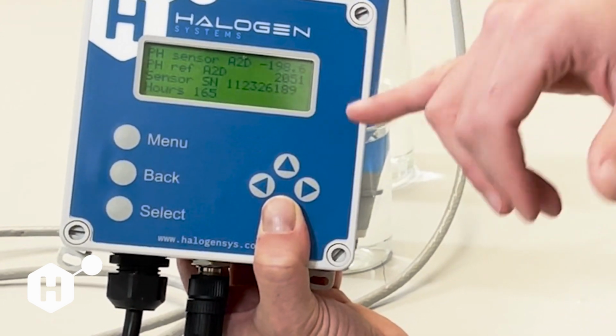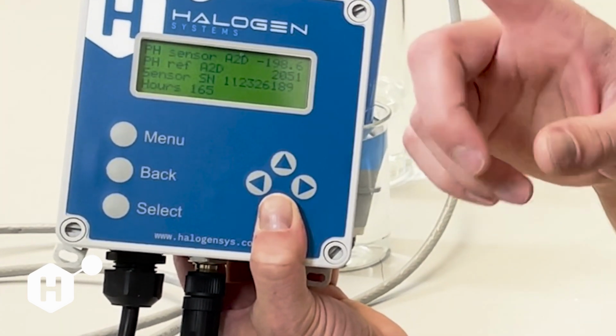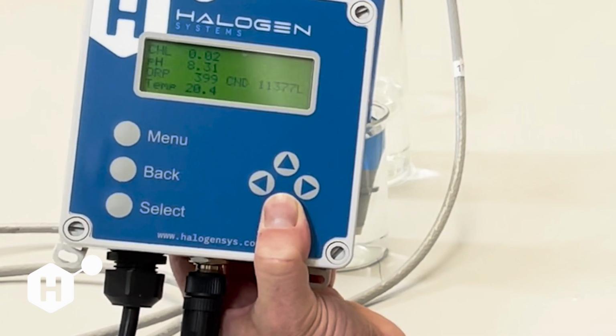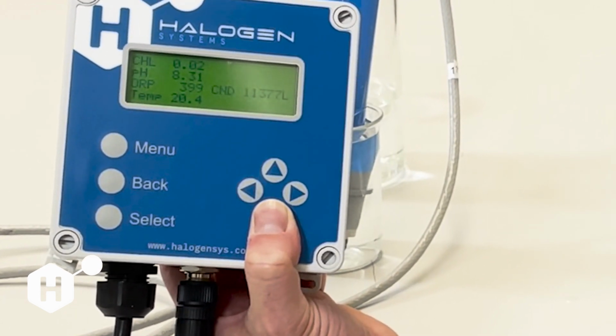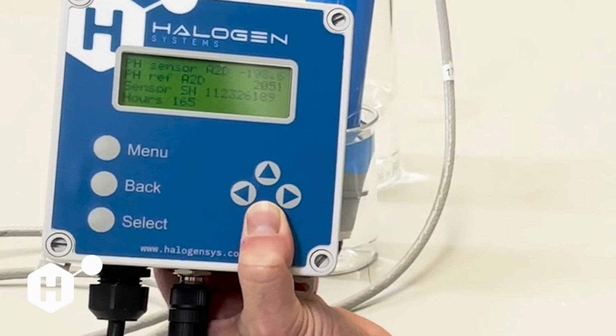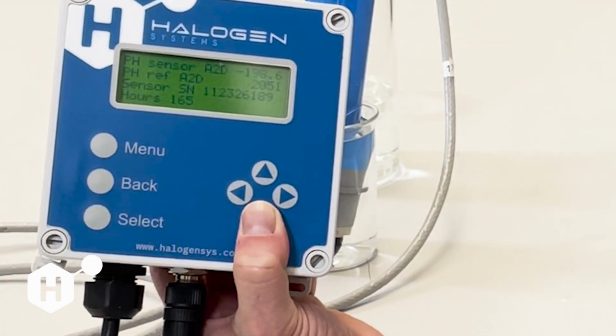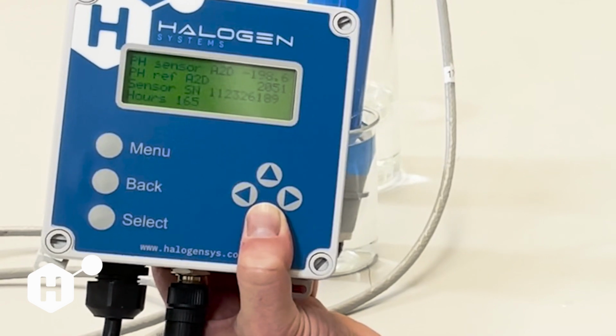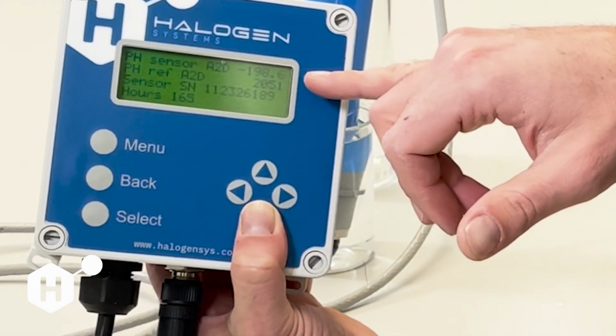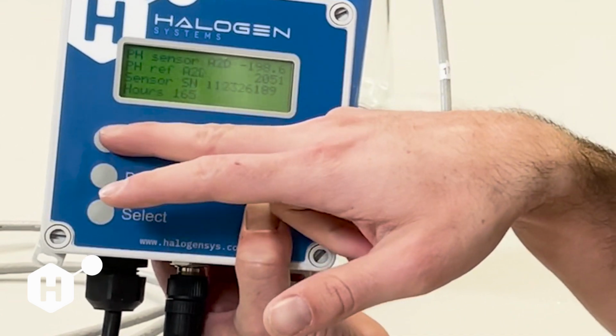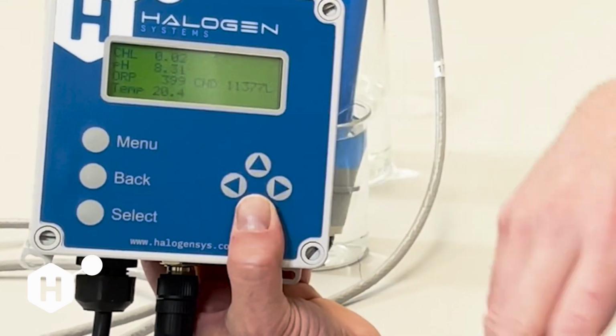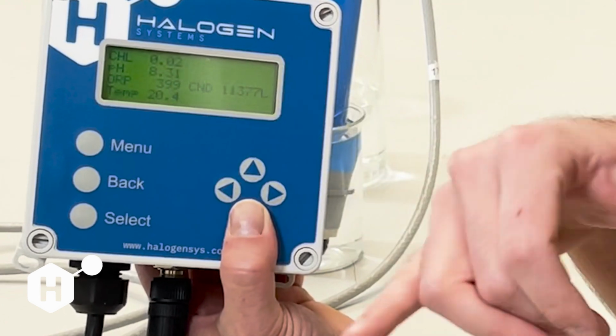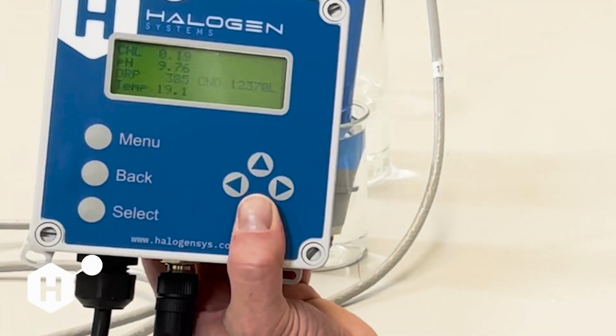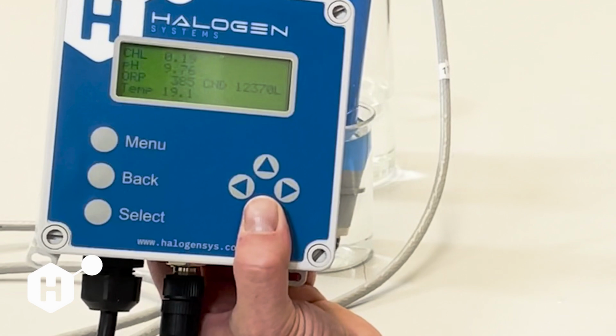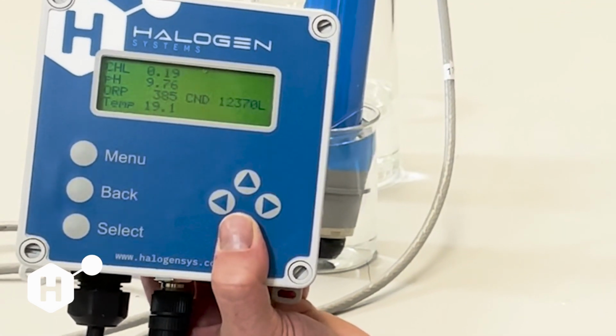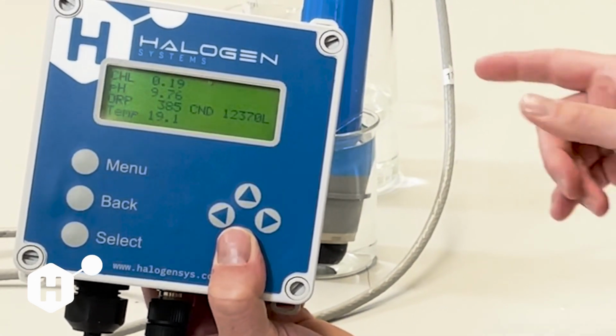I'm going to give it one more cycle just to confirm that that value is not jumping or moving at all before I initiate a calibration. And again, if you have averaging turned on or averaging a couple of cycles, you'll see this pH A to D change every cycle, but you might notice that your pH value doesn't change quite as quickly because it's averaging to whatever those previous cycles were. In our case, it was about 7 buffer. That won't have an effect on the calibration. The calibration is done entirely off of the pH sensor's raw millivolt reading.